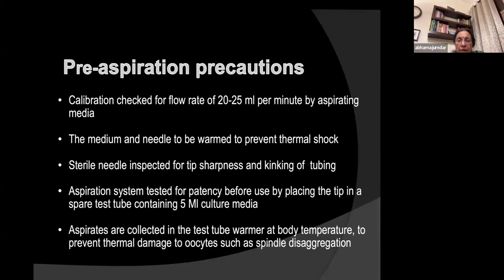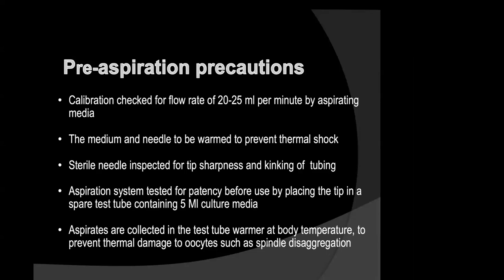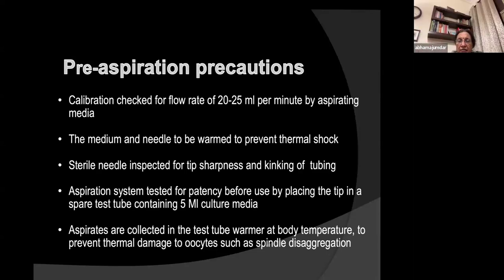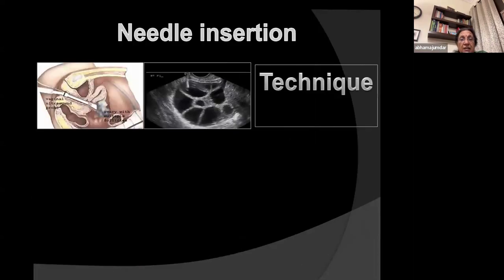Aspirates are collected in a test tube warmer at body temperature. So these tubes are inside the warmer and the connection goes on the cap on the tube, which is in the warmer. So all the fluid is collected in the warmer, which we set 1 degree higher than body temperature, that is at 38.5 or 39, because room air keeps cooling everything very fast. So as soon as the fluid goes in, the connection is separated, the cork is put into another tube with the whole system which connects the needle, and that tube is closed and handed over to the warmer in the embryology lab, which takes hardly 5 seconds. This prevents thermal damage to oocytes, which can lead to spindle disaggregation if there is a lot.